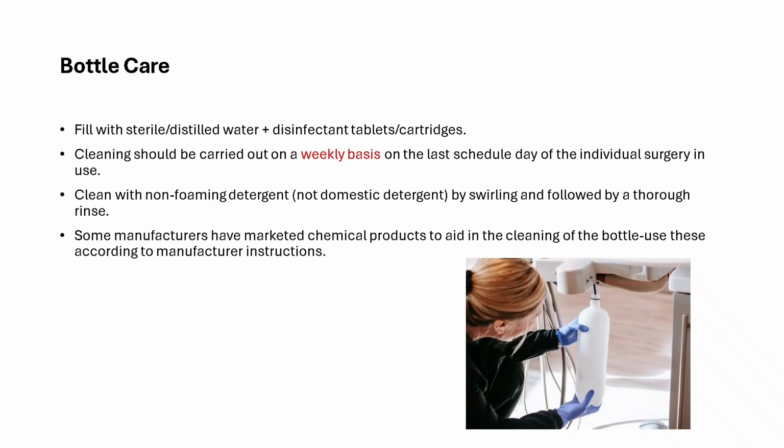Cleaning of the bottle is very important and should be done on a weekly basis on the last scheduled visit of the week. So you can clean the bottle with a non-foaming detergent and make sure you rinse it out with water. You can use a brush as well to clean the neck. There are some chemicals available commercially to also clean the bottles.